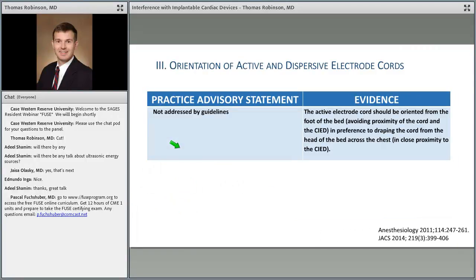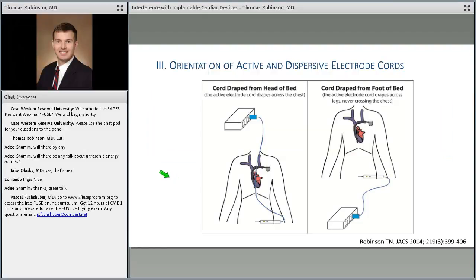All right, the next one is orientation of the active and dispersive electrode cords. This isn't addressed by the guidelines, but it turns out the tip of the active electrode, the tip of the pencil, that same energy that's given off there is also traveling all along your cord. So you should not drape your active electrode or your dispersive electrode cords adjacent or close to the patient's chest where the cardiac rhythm management device is. Instead, you should drape them from the foot of the table.